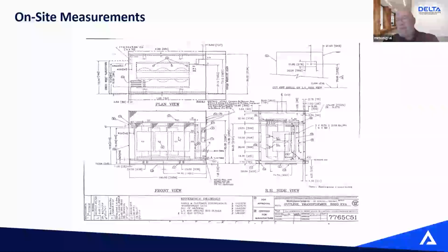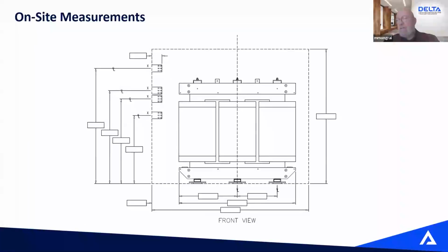So it's also a good practice to do a shutdown and to make sure that the information on the shop drawing is still accurate. If there's no availability of the existing shop drawings or information, Delta have developed over the years forms that we use when we do a shutdown. Depending on your busing arrangement, if the LV is on the left or on the right, same for the HV, and whether the bus is front to back or top to bottom, we have all kinds of forms that you and your contractor can use, while doing the shutdown, to take all the proper measurements so that we know exactly where the new transformer will need to connect on the existing equipment.